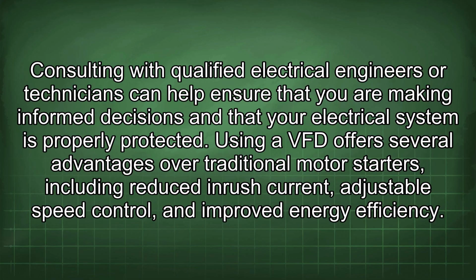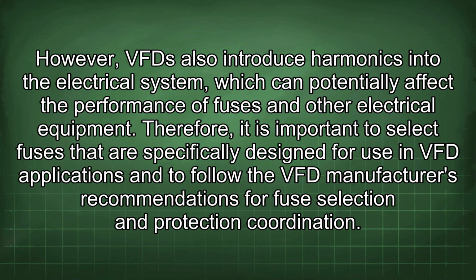system is properly protected. Using a VFD offers several advantages over traditional motor starters, including reduced inrush current, adjustable speed control, and improved energy efficiency. However, VFDs also introduce harmonics into the electrical system, which can potentially affect the performance of fuses and other electrical equipment. Therefore, it is important to select fuses that are specifically designed for use in VFD applications and to follow the VFD manufacturer's recommendations for fuse selection and protection coordination.